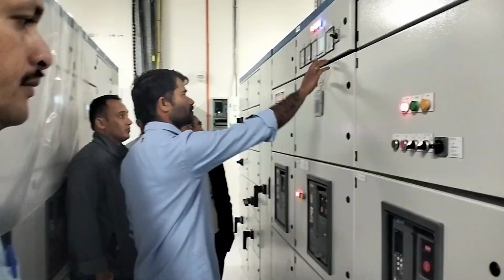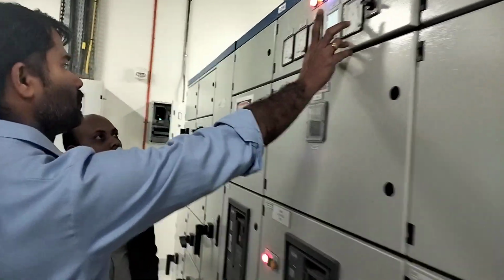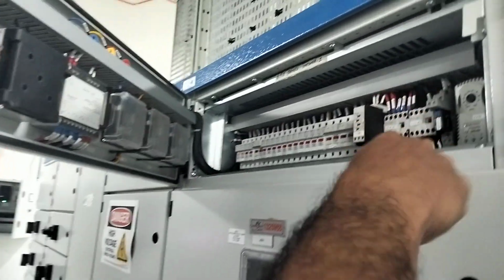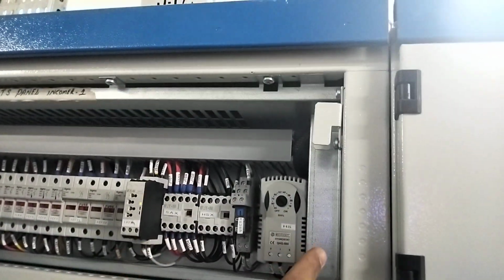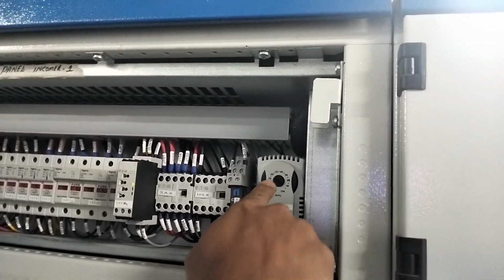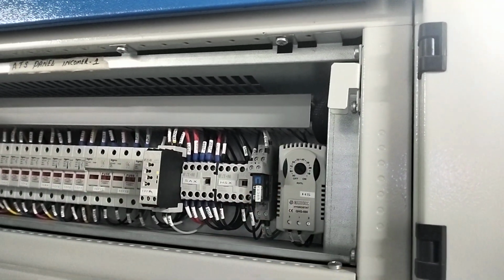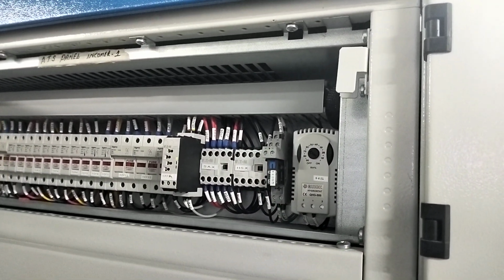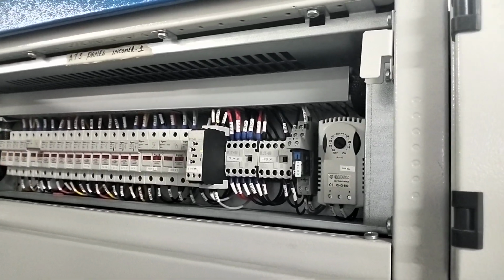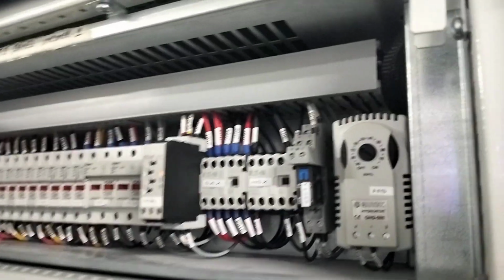Then this is a multifunction meter. You can get all the details here: voltage, current, power, and the 3 ammeter you have here, and 3-phase control. Then the humidity. If humidity is high, it's set, the heater is set at 60%. If the humidity goes more than 60, the heater will come on automatically and maintain the temperature.